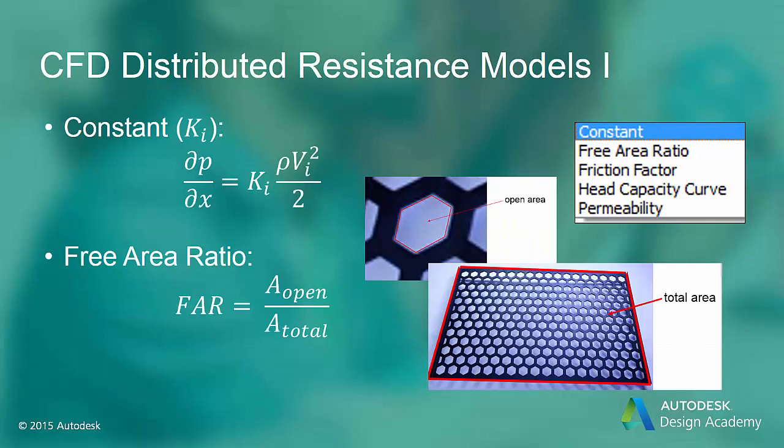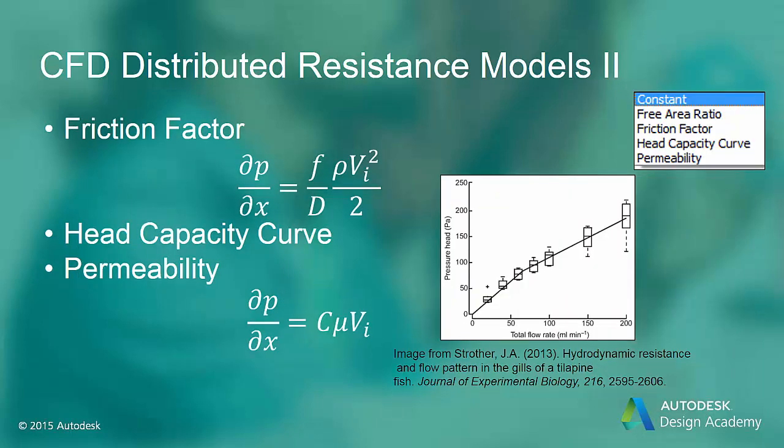There are several ways to represent the distributed resistance. In the constant method, you would provide the K value directly — this value may be provided by a manufacturer. In the free area ratio method, you specify the ratio of the total open area to the total area of the screen or perforated plate, a number between 0 and 1, which is used to calculate the K value. In the friction factor method, you provide data to calculate the friction factor based on the Moody chart, which works well for a tube bank such as in the OTSG. In the head capacity curve method, you provide a table of pressure drop versus flow rate to calculate a K value. The permeability model is a Darcy relation, typically used for soil or cloth, where the permeability coefficient C is specified.